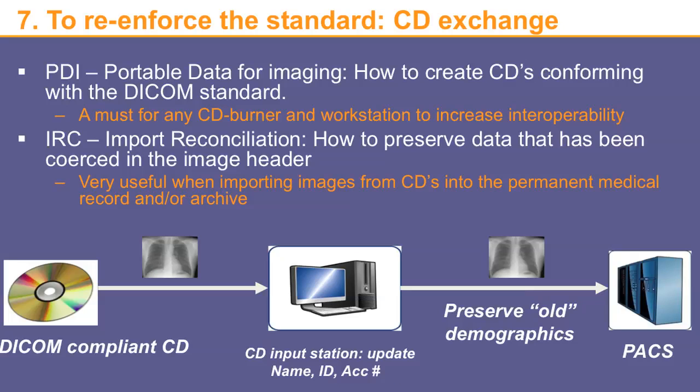The next benefit would be CDs — also a potentially major source of problems. Anyone involved in PACS systems knows that when you get a CD from another hospital, there's always a chance you might not be able to read the images, for various reasons. The images might not be encoded in DICOM, there might not be a directory, or they might not be encoded according to ISO standards. The PDI, Portable Data for Imaging Profile for IHE, reinforces the information in the DICOM standard that says how to encode these images on the CD.